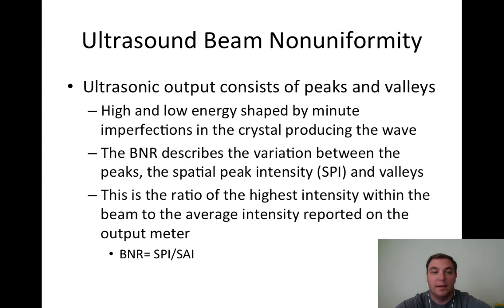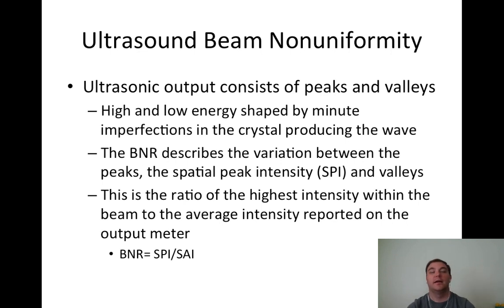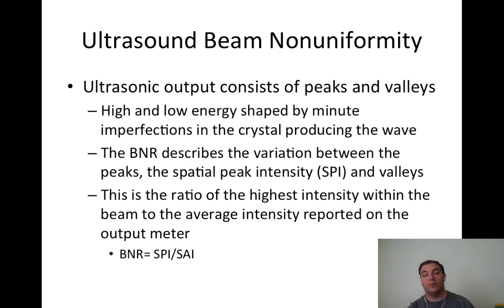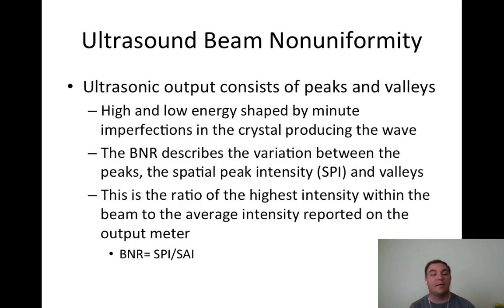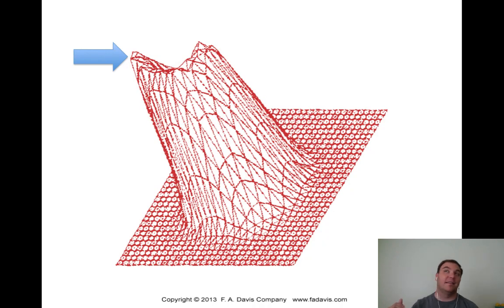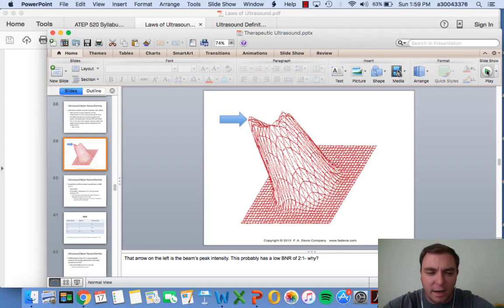Ultrasound beam non-uniformity: BNR. The ultrasound output consists of peaks and valleys - high and low energy shaped by minute imperfections of the crystal. The BNR describes the variation between the peaks and valleys, and is the ratio of the highest intensity within the beam to the average intensity on the output meter. BNR equals spatial peak intensity divided by SAI. A high BNR ratio can actually cause tissue damage and burns.